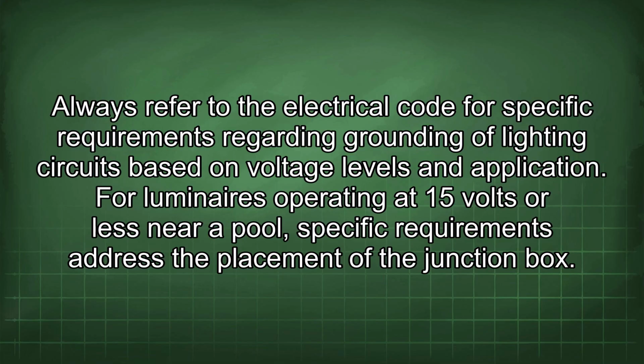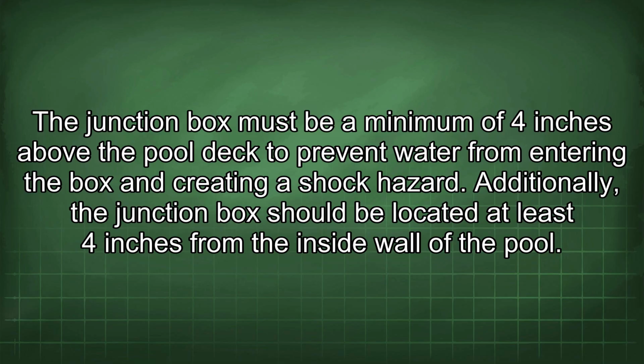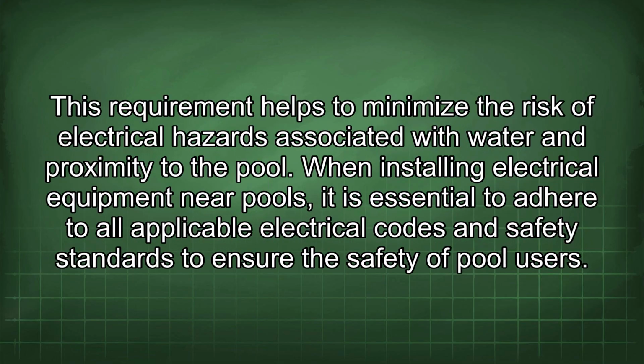For luminaires operating at 15 volts or less near a pool, specific requirements address the placement of the junction box. The junction box must be a minimum of 4 inches above the pool deck to prevent water from entering the box and creating a shock hazard. Additionally, the junction box should be located at least 4 inches from the inside wall of the pool. This requirement helps to minimize the risk of electrical hazards associated with water and proximity to the pool. When installing electrical equipment near pools, it is essential to adhere to all applicable electrical codes and safety standards to ensure the safety of pool users.